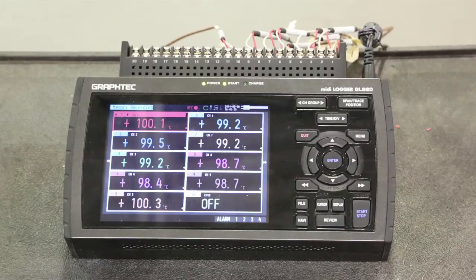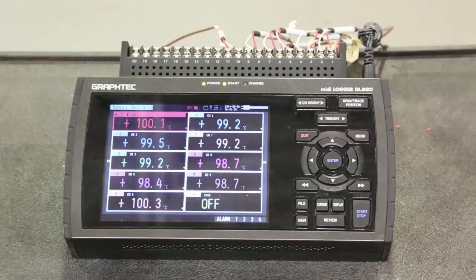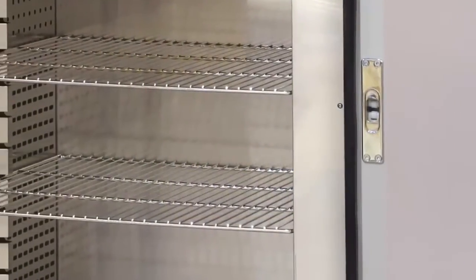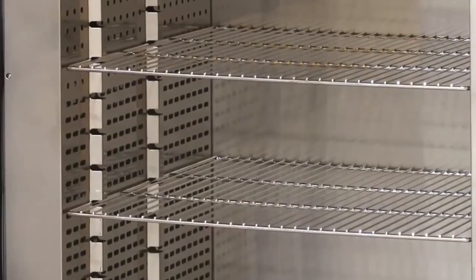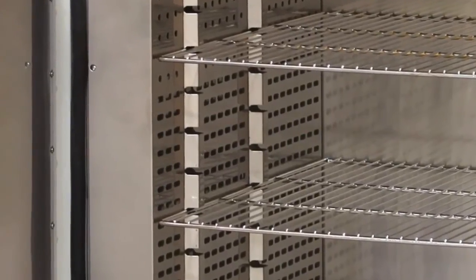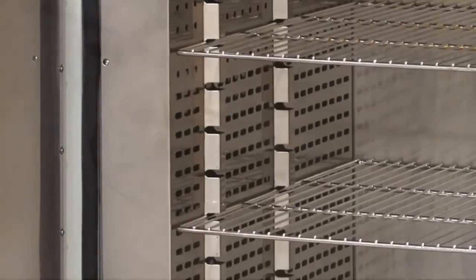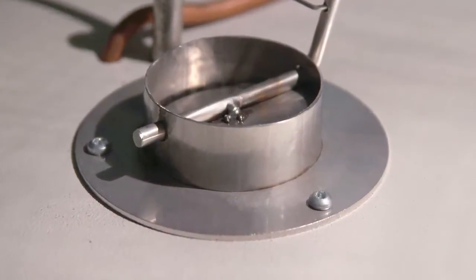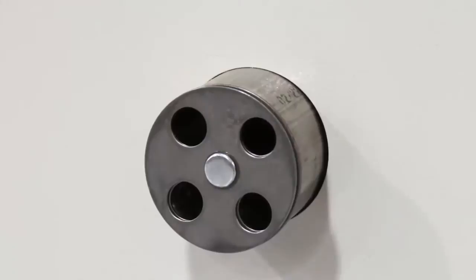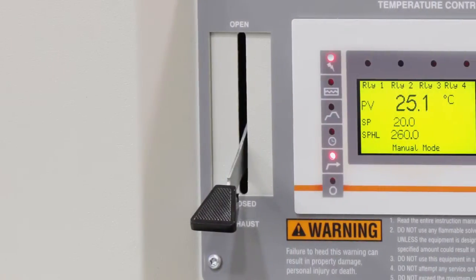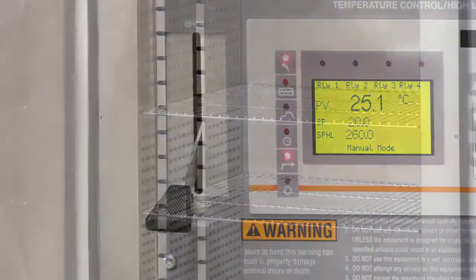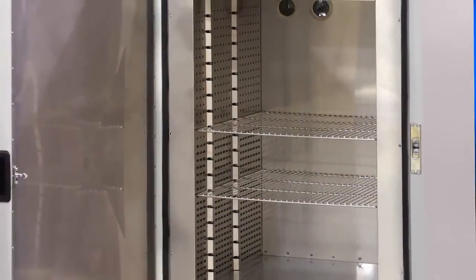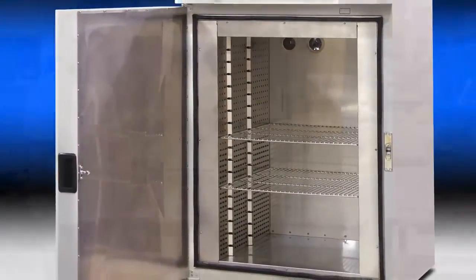If you find that your oven is not delivering the expected uniformity, there are a number of things to check that could be affecting the results. Check the door seals to make sure you are getting a proper seal. Examine the louvers to make sure they are not blocked. Ensure that the recirculation fan is working properly. Check for problems with the fresh air and exhaust damper. Your chamber pressure needs to have neutral to slightly positive pressure to achieve expected uniformity. If that doesn't address the problem, it could be poor wall insulation causing the oven to lose too much heat.